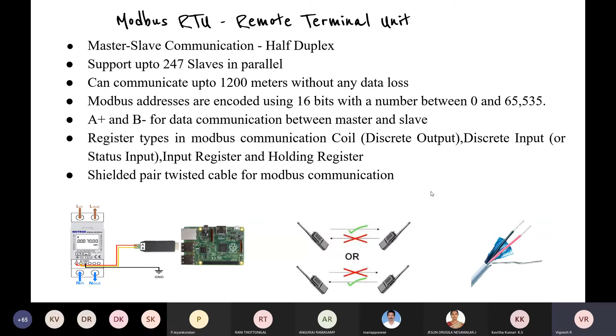Another main thing is that we should use a shielded twisted pair cable for Modbus communication to get the data without any loss. In this picture you can see what a shielded twisted pair cable looks like. The black and red are the wires, and the blue and gray are supporting parts that hold the twisted pair inside the cable. By using this cable, we can get data without any loss up to 1200 meters.